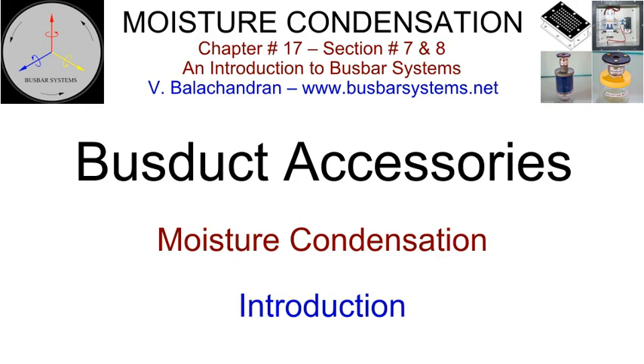Introduction. Moisture condensation can occur inside a metal enclosed air-insulated busbar system whenever the temperature dips below the dew point. Condensation occurs when warm, moist, still air comes in contact with a cold surface. The cold surface chills the air to below the dew point, resulting in moisture condensation.